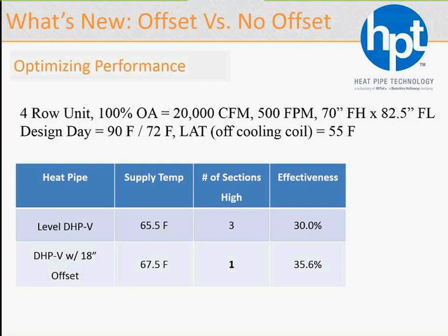As we create this offset, in this particular case 18 inches, we go from 65.5 to 67.5, significantly here with one section and with an effectiveness of 35.6%. That's a 19% increase, a pretty significant increase. Any questions so far? We good? Okay. John is signaling that we're good. So that pretty much wraps up our wraparound part of this presentation.